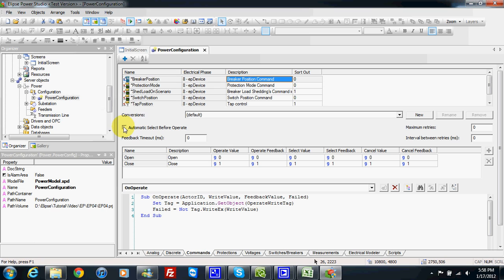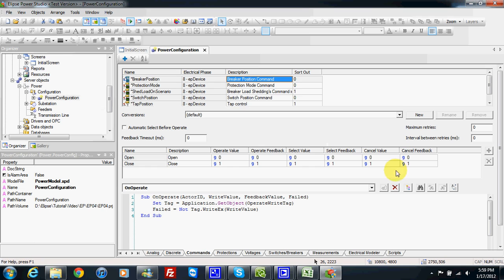We have operate and operate feedback. When we send the operate value, the system will reply with the operate feedback. The same applies to select — if we first make a select value, we get select feedback. Then we make the operate value and get operate feedback. Also, if the command is cancelled between select and operate, we can also read feedback from the device. Each relay or equipment may have different values when we send the command open or close for the three stages: operate, select, and cancel.